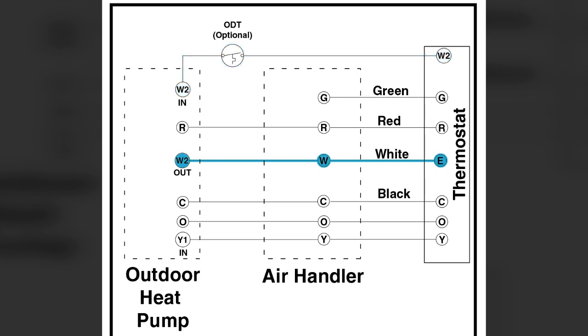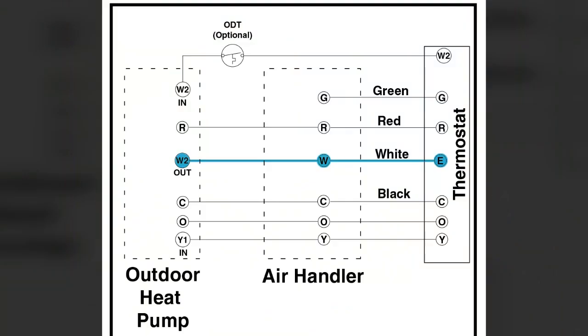So what we show here is E going to W on the air handler. That's emergency heat. So most of your better heat pump thermostats will have an emergency heat selection on the selector switch. When you select that to emergency heat, what that does is it overrides the heat pump, shuts it off. The heat pump will not function. And then it becomes a single stage thermostat that energizes the E terminal and turns on and sends power to W, which turns on your electric heat. And that's the only thing that'll function is your electric heat.